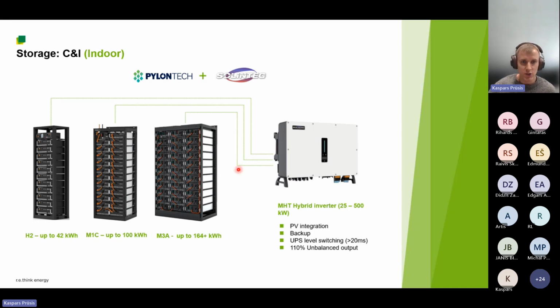For example, with such systems, you can create a solution with capacities up to 164 kilowatt hours. You can multiply this by how many battery stacks or racks you want to have, plus the Solinteg hybrid inverter, which can have output power starting from 25 up to 500 kilowatts. So this is really a good and, I would say, cost-effective solution, which allows you to easily integrate PV into it.